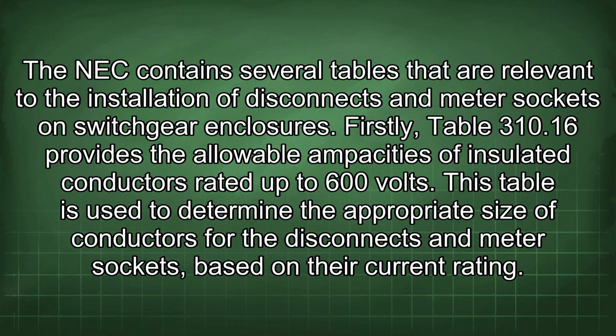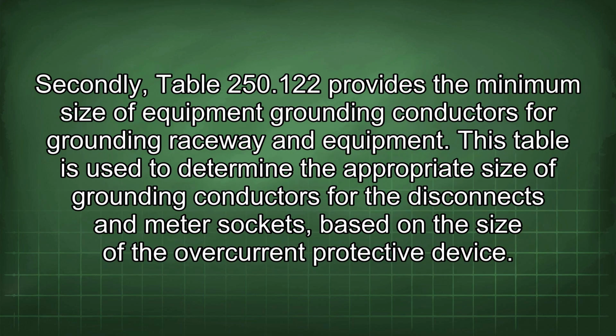Firstly, Table 310.16 provides the allowable ampacities of insulated conductors rated up to 600 volts. This table is used to determine the appropriate size of conductors for the disconnects and meter sockets based on their current rating. Secondly, Table 250.122 provides the minimum size of equipment grounding conductors for grounding raceway equipment. This table is used to determine the appropriate size of grounding conductors for the disconnects and meter sockets based on the size of the overcurrent protective device.